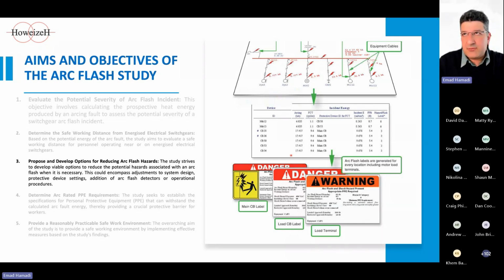So the protection setting, yes, is a way of doing that, but it just gives you limited room to maneuver, if you like. If you want to go further, you need to use other measures like the arc flash detection system, which operates independently of the protection system and can trigger in case of an arc flash.